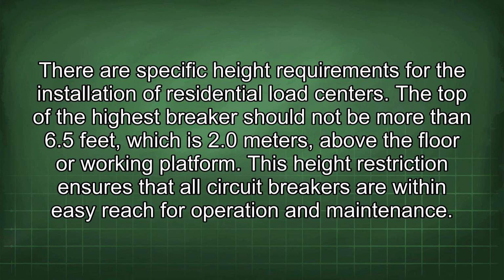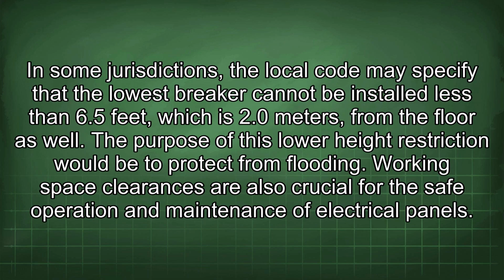There are specific height requirements for the installation of residential load centers. The top of the highest breaker should not be more than 6.5 feet, which is 2.0 meters, above the floor or working platform. This height restriction ensures that all circuit breakers are within easy reach for operation and maintenance. In some jurisdictions, the local code may specify that the lowest breaker cannot be installed less than 6.5 feet, which is 2.0 meters, from the floor as well. The purpose of this low height restriction would be to protect from flooding.